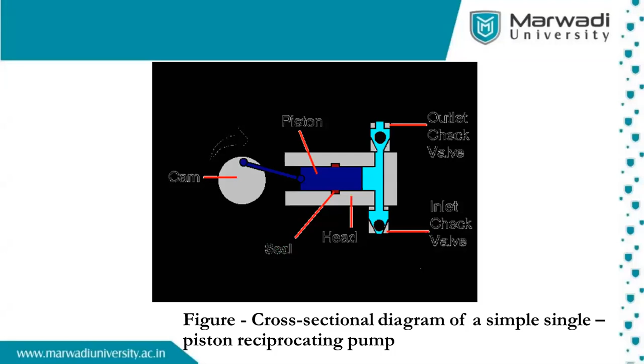Next. So this is a small picture of the reciprocating pump, and it is very important, because this pump gives the exact flow. For example, 2 ml per minute, it will give exactly 2 ml per minute only. That is the accuracy you can achieve with the help of the reciprocating pump, as well as pressure. So that is the reason we are using the reciprocating pump.